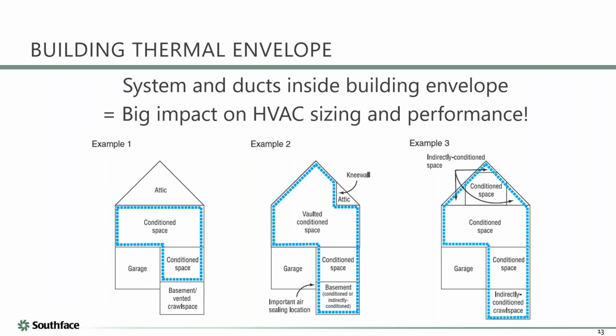Okay, moving on. Also, let's just get this out of the way up front, Joey. The single biggest design decision that you can make that will impact the efficiency of your heating and cooling is where you put the ductwork and the mechanical systems. And I feel like all these design decisions work their way into home design or home renovation, and I'm just like, are you really appreciating how important this is? So we've hammered this before, but in a nutshell, if you have a duct system in each of these three homes, and there's one up here where X is located, and there's one down here where Y is located. House number one, both duct systems are outside the conditioned envelope. House number three, both duct systems are inside the conditioned envelope. If everything else is equal in here, house number three is going to outperform. And it's because the ducts and the air handlers are inside.